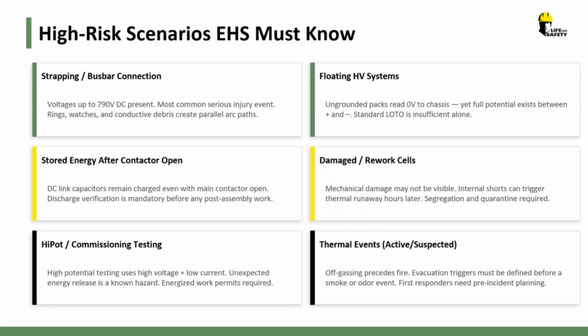Matt, on these high risk scenarios, can you share an example of how a routine task can quickly become a high voltage incident? Yeah -- dropped bus links, the little links you tie together when connecting what we call the high voltage chain, HV chain. I've had two or three incidents where a fairly new person, arguably wearing the right voltage-rated gloves, dropped the links or hooked one up incorrectly for positive, negative polarity, and caused a massive event.